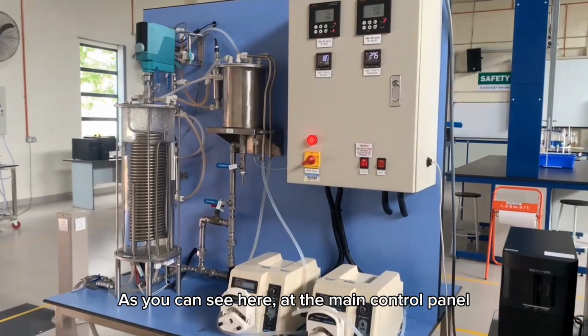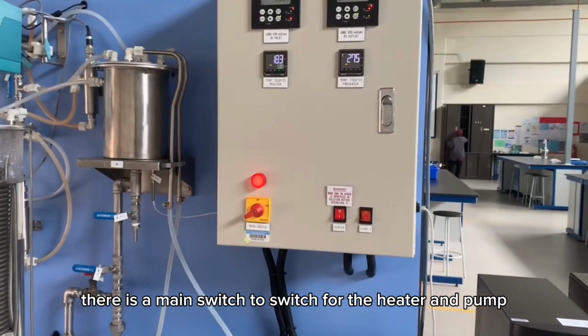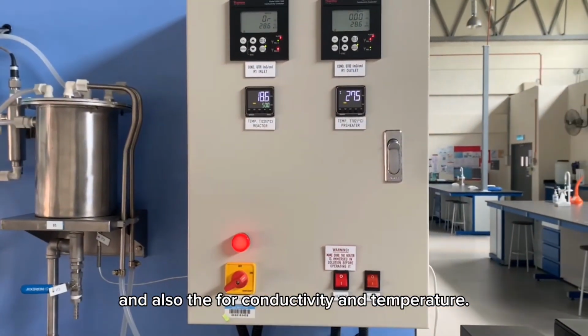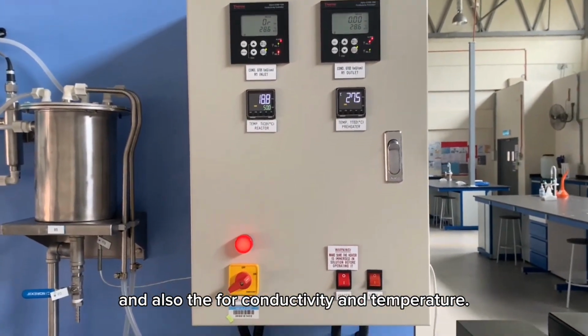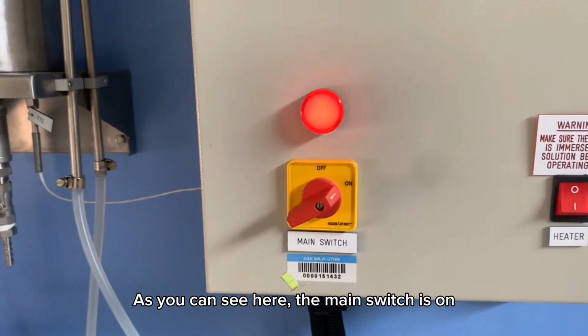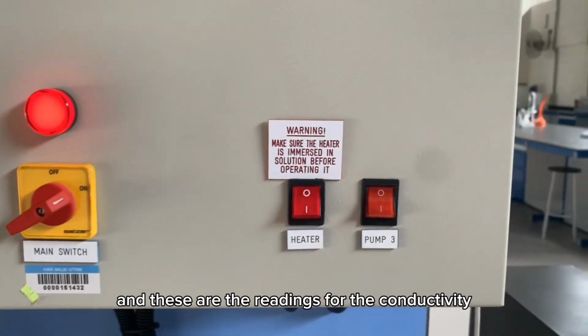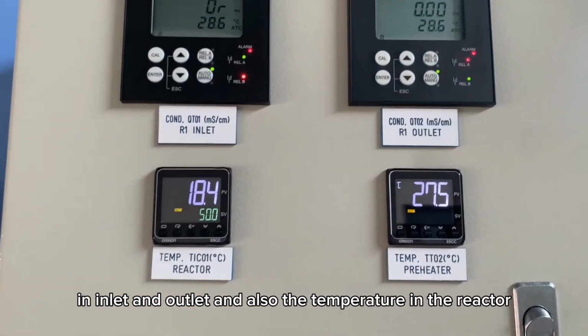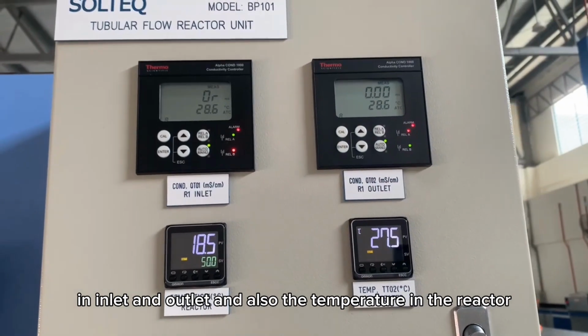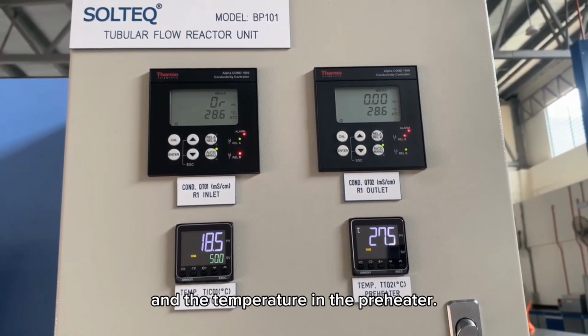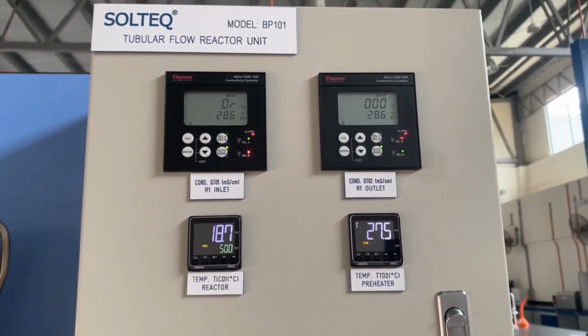As you can see here at the main control panel, there is the main switch, the switch for the heater and pump, and also the reading for conductivity and temperature. As you can see here, the main switch is on, and these are the readings for the conductivity in the inlet and outlet, and also the temperature in the reactor and the temperature in the preheater.